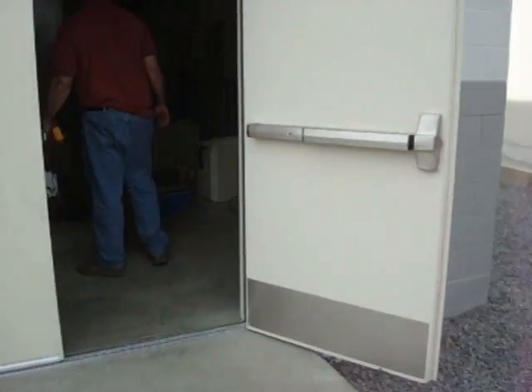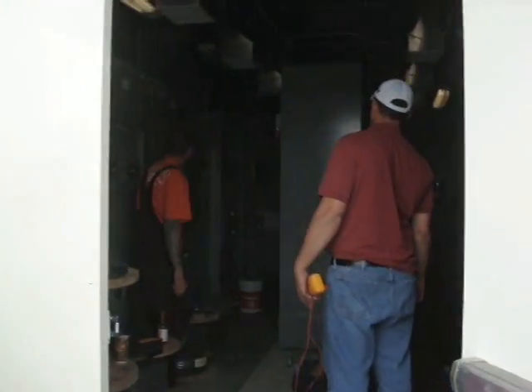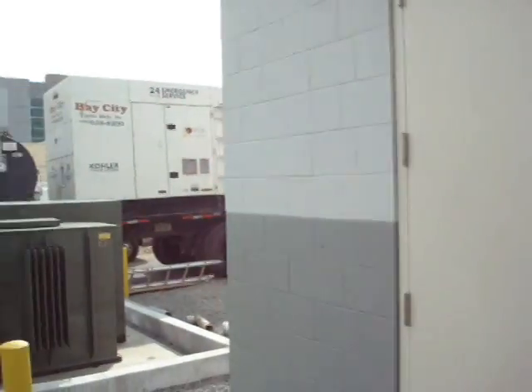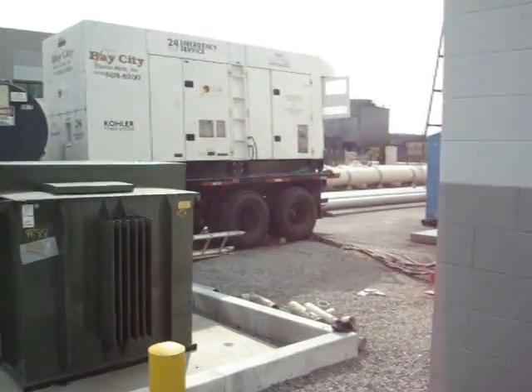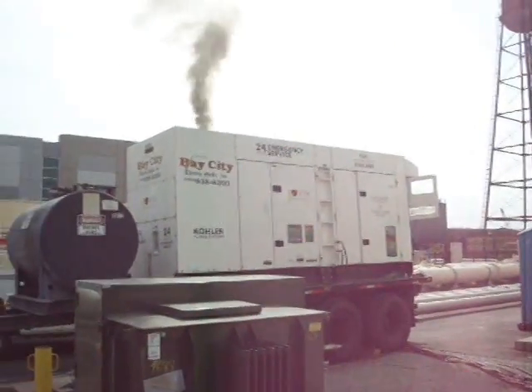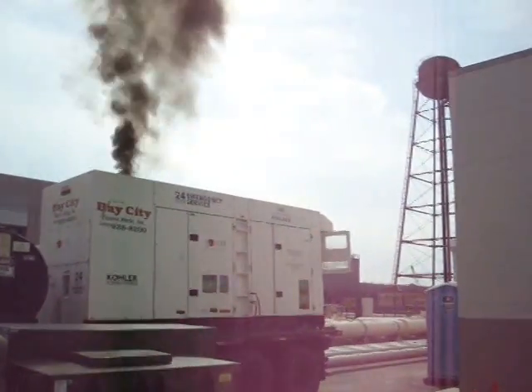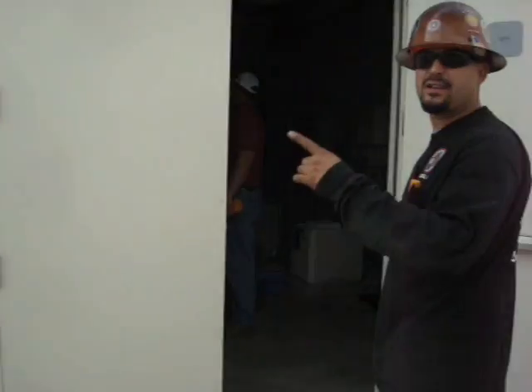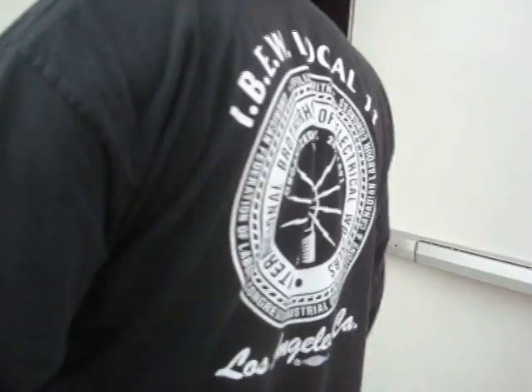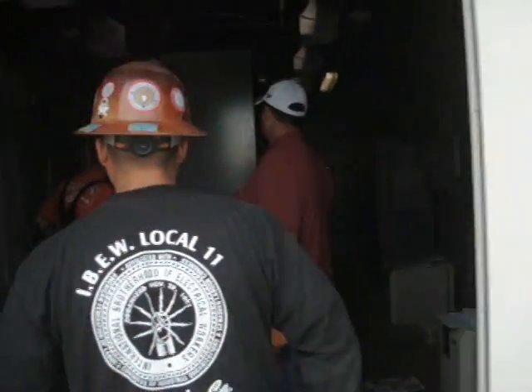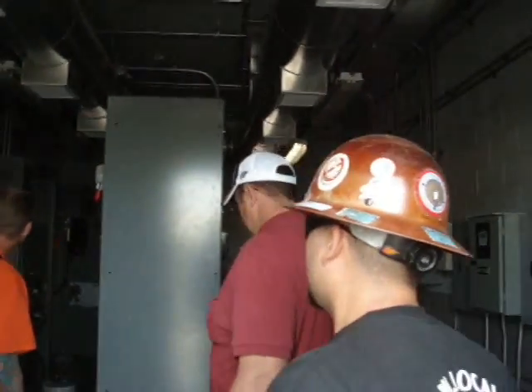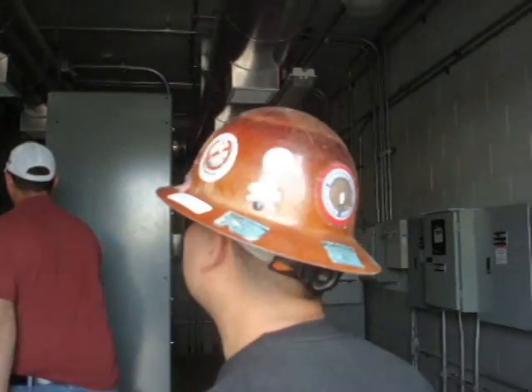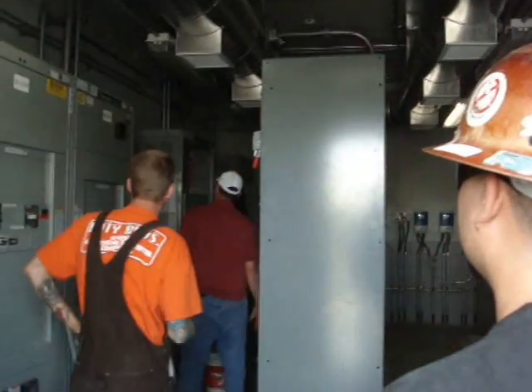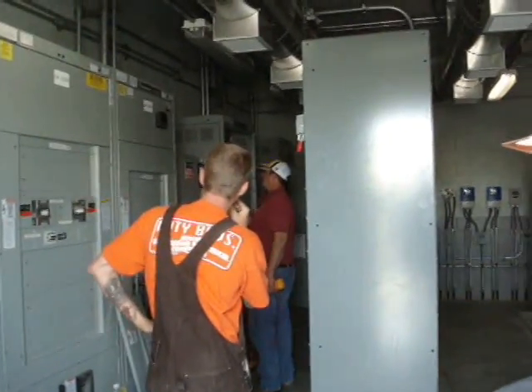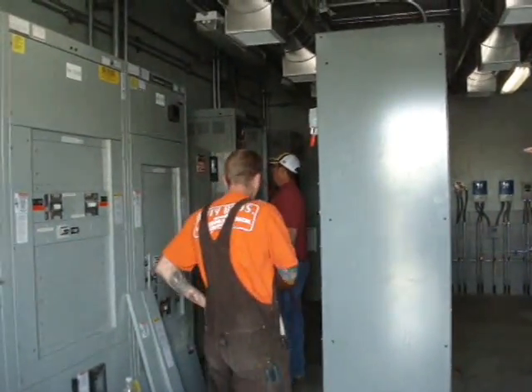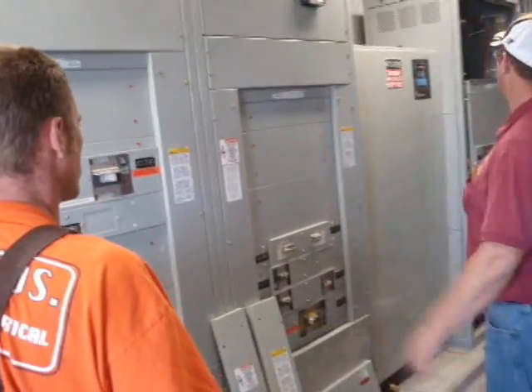Part of our documentation included the automatic startup of backup generation. We had to use a portable generator because we couldn't get a permit for the permanent generator. And this involved extra time, extra work. We had to set up the portable generator so that it would receive a start signal and controls from the transfer switches in the interior here. So we had to work through a number of different issues.